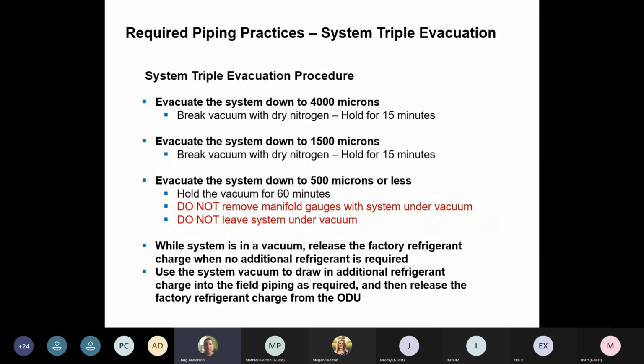So what we want to do is bring our vacuum gauge down to 4,000 microns. We want to hold it for 15 minutes. Then we want to break it with dry nitrogen. So we're drying the line a little bit more, getting more moisture out of it. Bring your vacuum down to another 1,500 microns. Hold it for 15 minutes. Break it with dry nitrogen again. We're drying it some more.